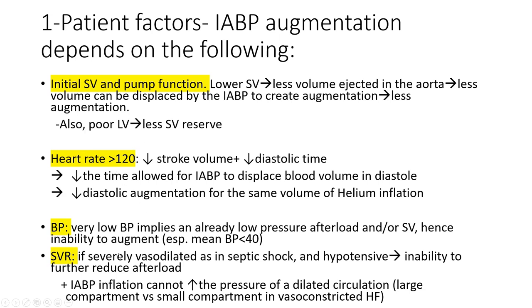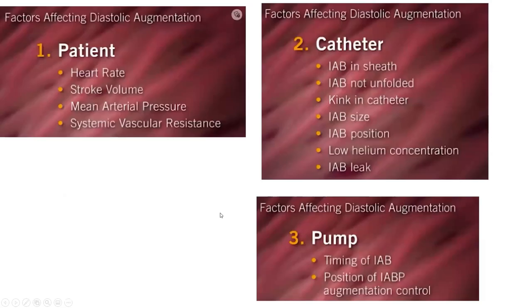especially the sickest MI shock patient. SVR: to respond to balloon pump, the more you're vasoconstricted, the more you respond to balloon pump, because the more you're vasoconstricted, the smaller your vascular arterial compartment is, and the more you will get a bump in pressure upon augmentation and displacement of blood volume. So if you're severely vasodilated, as in septic shock and hypotensive, there is inability to further reduce afterload. That's why, of course, balloon pump is not going to work in septic shock, because balloon pump cannot increase the pressure of a dilated circulation, of a large compartment. You need that small compartment of vasoconstricted heart failure to augment with balloon pump.